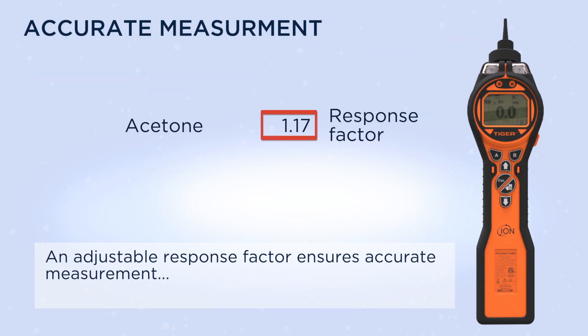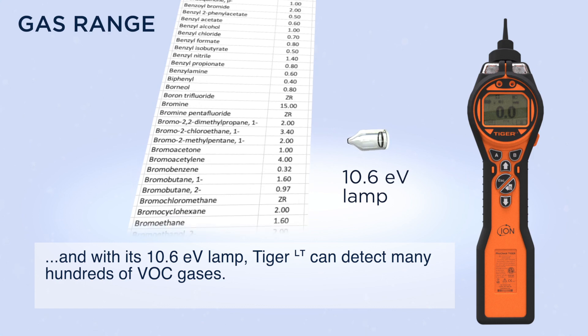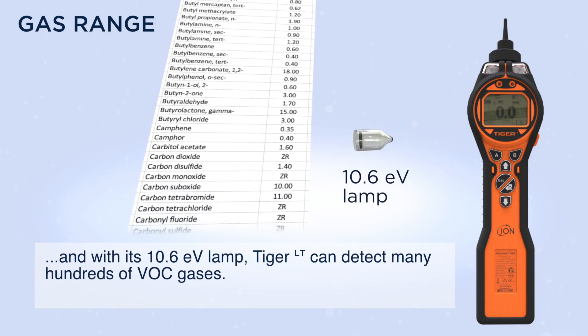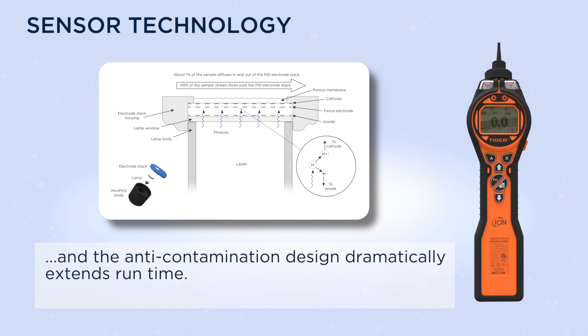An adjustable response factor ensures accurate measurement, and with its 10.6 eV lamp, Tiger LT can detect many hundreds of VOC gases. Its patented fence electrode sensor technology means the sensor is resistant to humidity, and the anti-contamination design dramatically extends runtime.